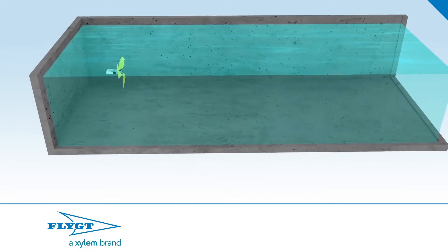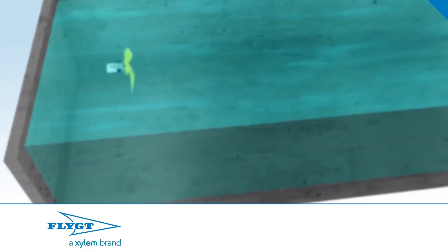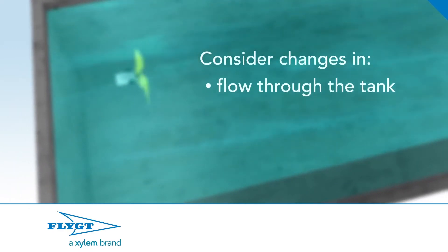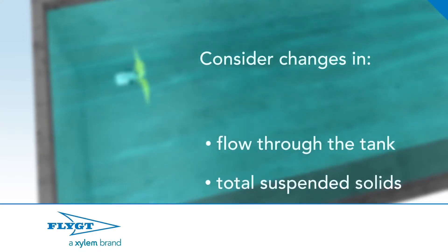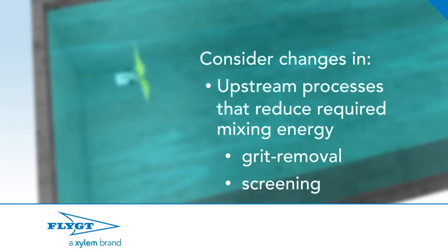So when is it appropriate to slow the mixing speed? You must consider changes in flow through the tank, the total suspended solids, and even the total amount of wastewater in the basin. All these changes, whether they happen hourly, weekly, or seasonally, are opportunities to save energy and reduce your carbon footprint, while extending service life and improving reliability.